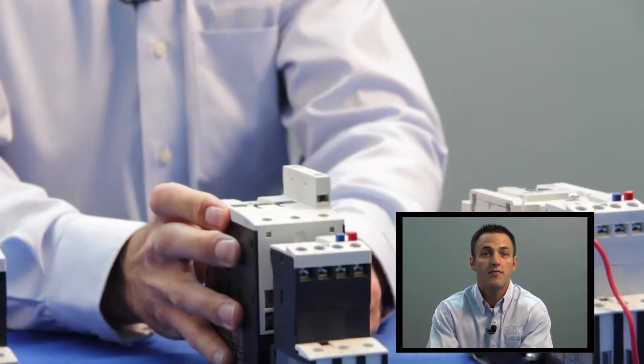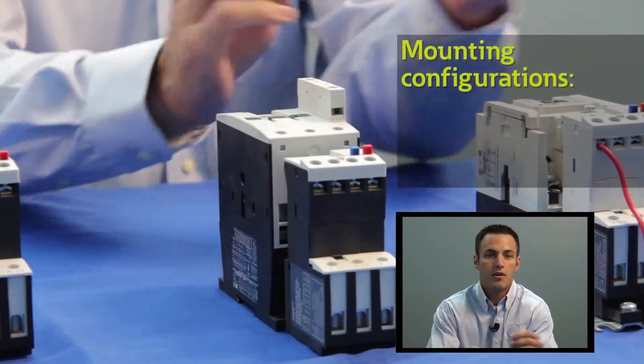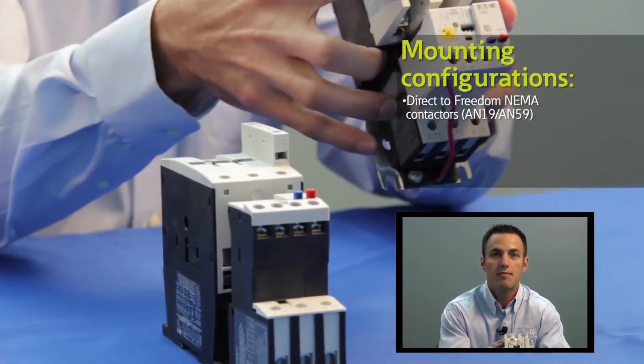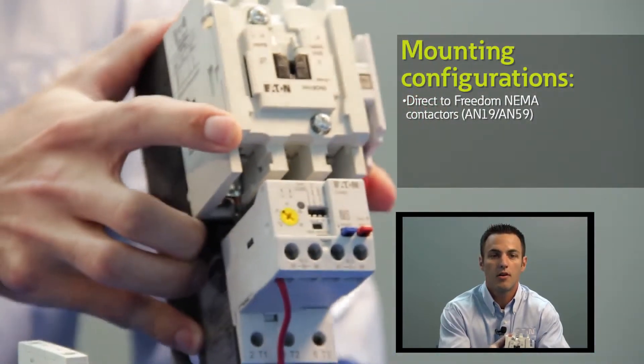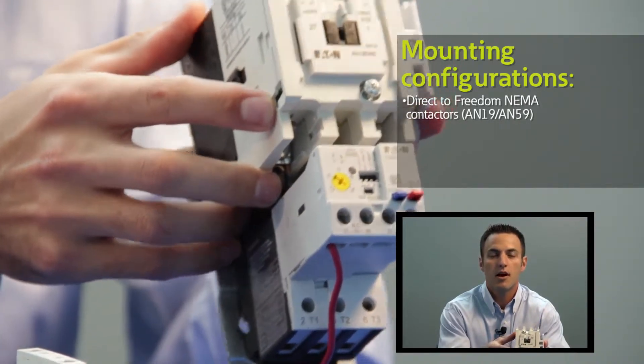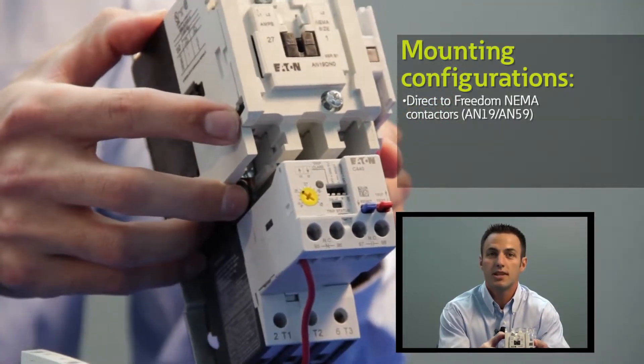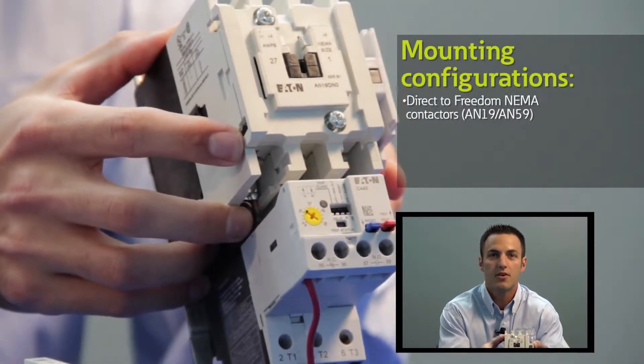There are actually four different mounting configurations available for this overload. The first is direct mounted to a NEMA freedom contactor up to 140 amps or a NEMA size 4. We designate this starter solution as the AN19. Above 140 amps we use external current transformers that can be used to cover ranges up to 1500 amps.